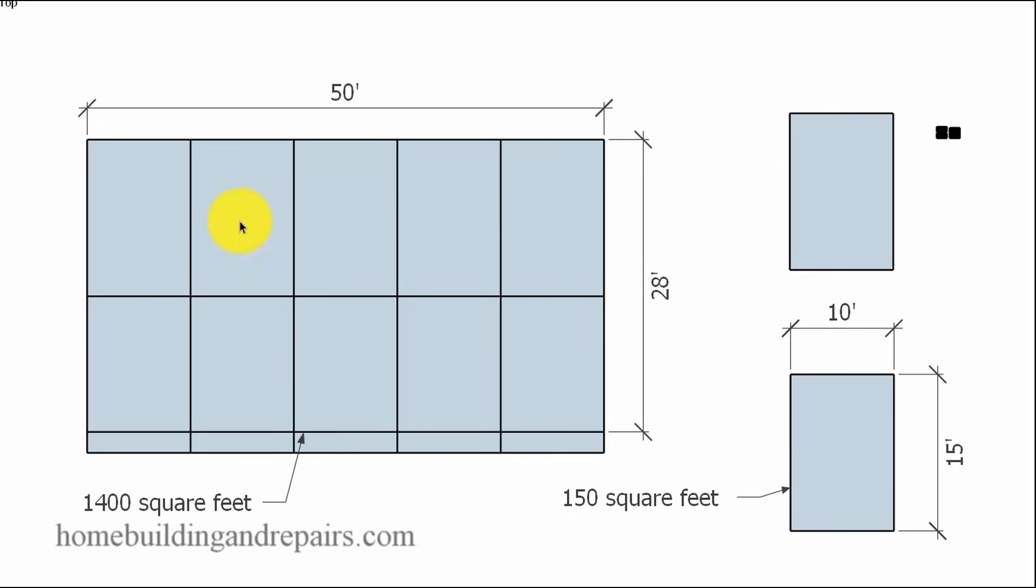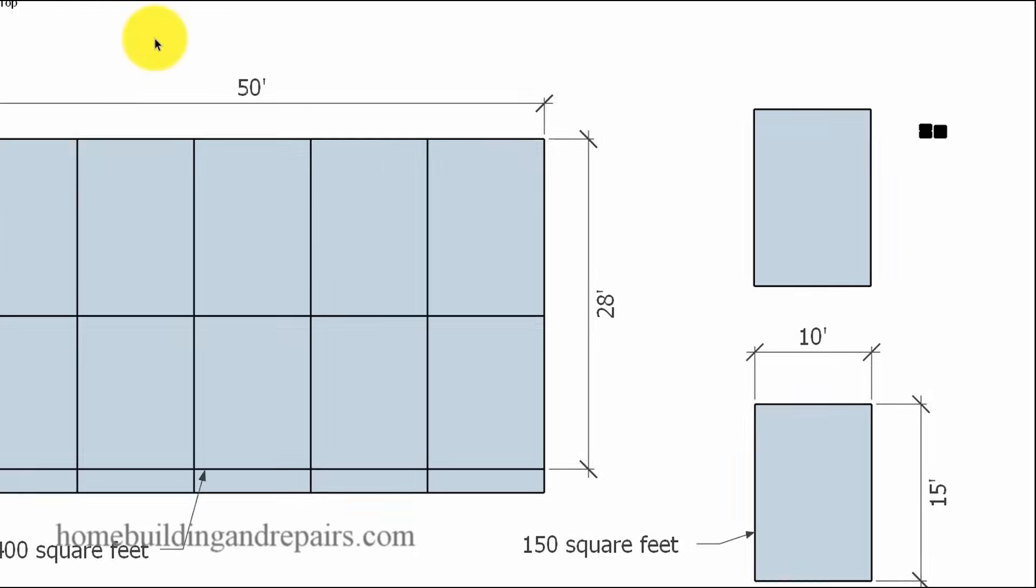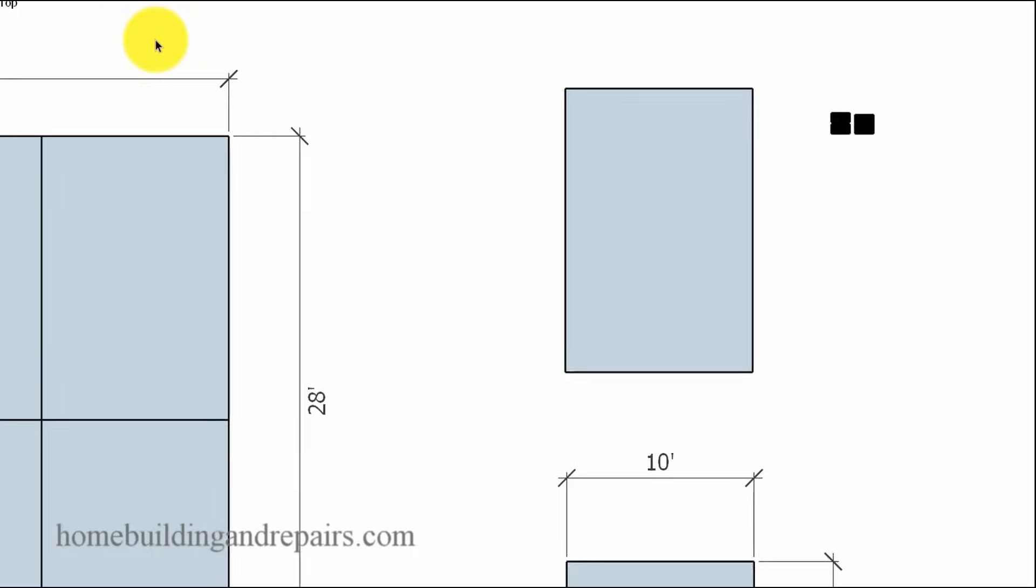So if you put 10 vents or 10 square feet of screened vent area in here, you would be just fine with this particular foundation. You can be a little larger. You just can't be a little smaller.